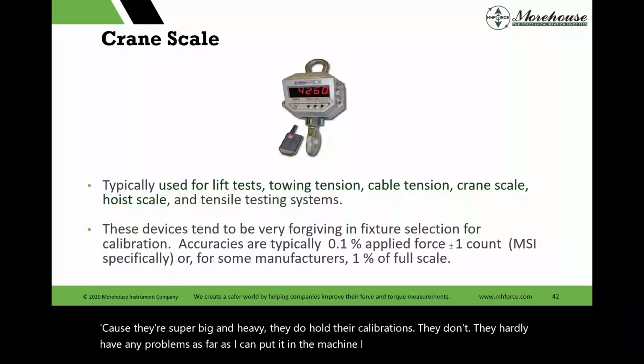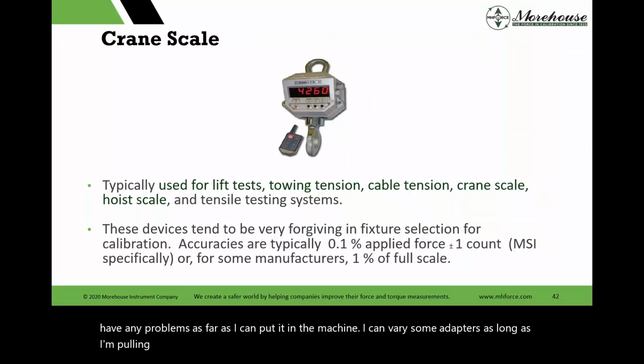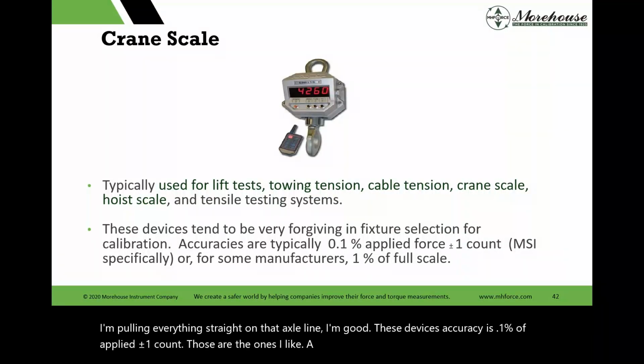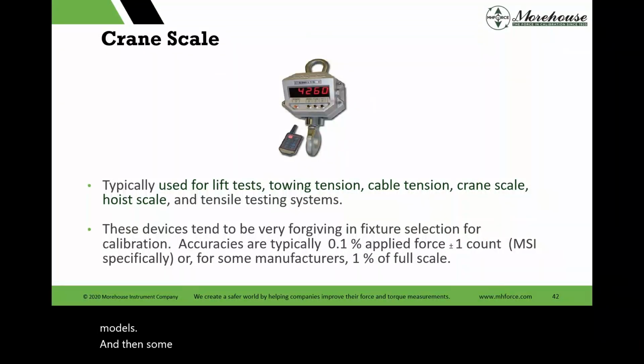They hardly have any problems as far as I can put it in the machine. I can vary some adapters. As long as I'm pulling everything straight on that axle line, I'm good. These devices, accuracy is 0.1% of applied plus or minus 1 count. Those are the ones I like a lot to get that extra 1 count. There's different models. And then some manufacturers, it's 1% of full scale. Like I said, they're just super heavy compared to the tension link.